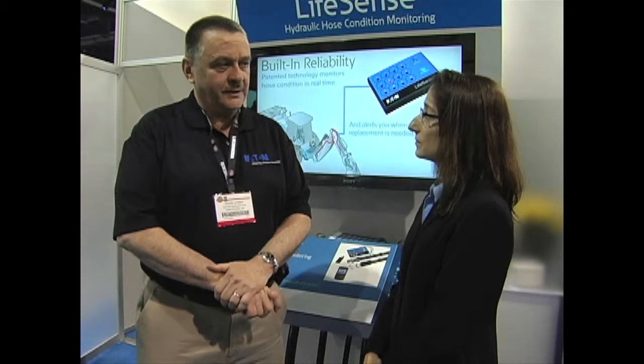Sure. A couple of years ago, one of our engineers was in the lab testing hydraulic hoses in our impulse tester, and he noticed some consistent feedback during his testing of the hose. He continued to test and experiment and found that as a hose approaches the end of its useful life, there is always a consistent pattern of events that occurs, and that we could measure that.